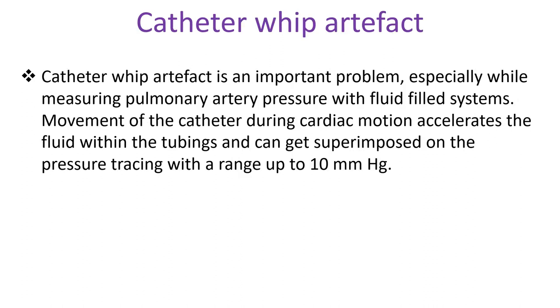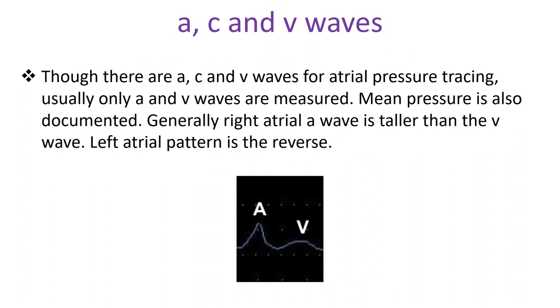Catheter whip artifact is an important problem, especially while measuring pulmonary artery pressure with fluid-filled systems. Movement of the catheter during cardiac motion accelerates the fluid within the tubings and can get superimposed on the pressure tracings, with a range of up to 10 mmHg.